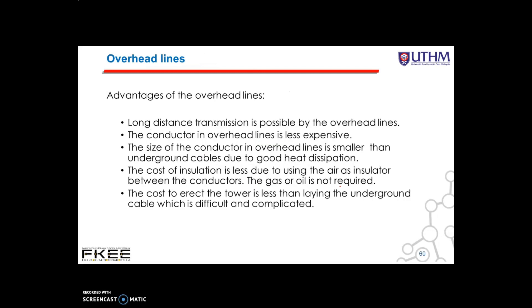The advantages of overhead lines are: long distance transmission is possible; the conductor in an overhead line is less expensive; the size of the conductor is much smaller compared to underground cables due to good heat dissipation; the cost of insulation is less since air is used as the insulator between conductors; gas or oil is not required; and the cost to erect the tower is less than laying underground cables, which is very difficult and complicated.